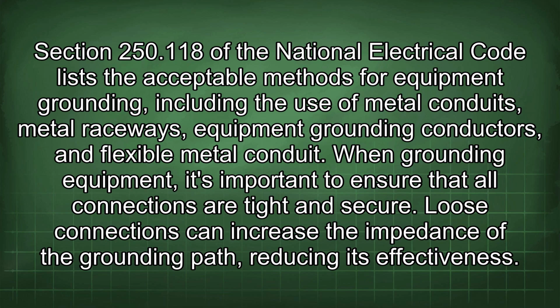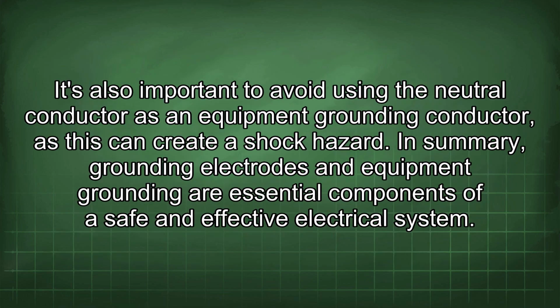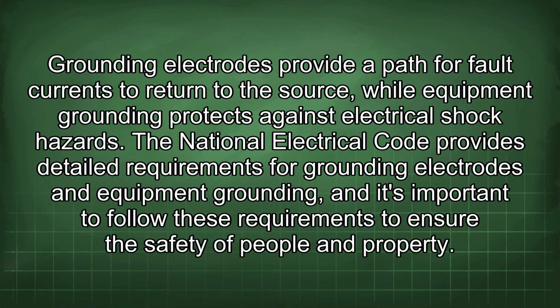When grounding equipment, it's important to ensure that all connections are tight and secure. Loose connections can increase the impedance of the grounding path, reducing its effectiveness. It's also important to avoid using the neutral conductor as an equipment grounding conductor, as this can create a shock hazard. In summary, grounding electrodes and equipment grounding are essential components of a safe and effective electrical system. Grounding electrodes provide a path for fault currents to return to the source, while equipment grounding protects against electrical shock hazards. The National Electrical Code provides detailed requirements for grounding electrodes and equipment grounding, and it's important to follow these requirements to ensure the safety of people and property.